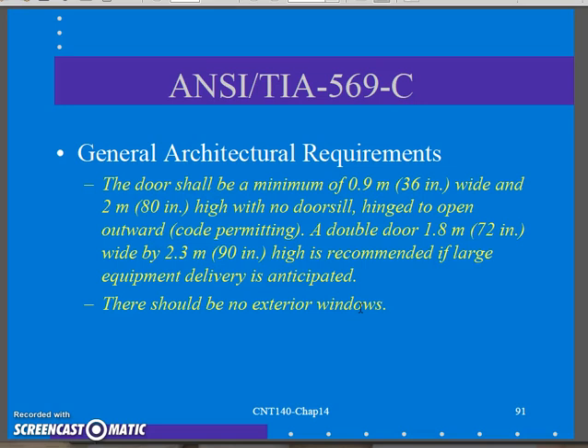Most doors are 30 to 36 inches. My house, being an old farmhouse, is about 29 and a half inches, which is a challenge — I have to take doors off fridges and handles off appliances just to get things in and out. Your closet should meet the minimums specified so you can get equipment in and out of the room. There should be no exterior windows, obviously for safety reasons — somebody could throw a brick through, climb in, and steal switches, routers, firewalls, or hard drives out of servers. With a RAID server, they could steal a drive or two and the server would never know it.